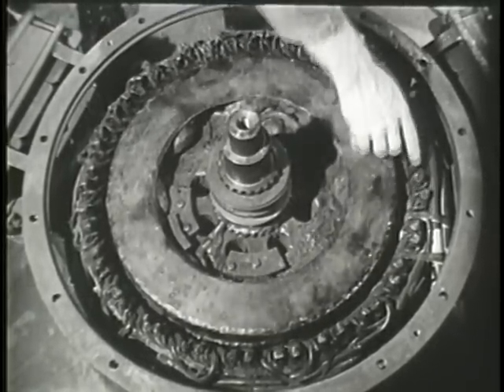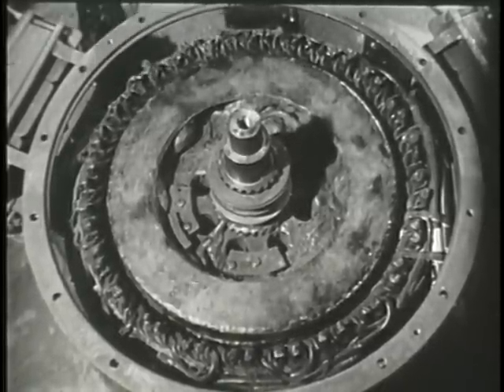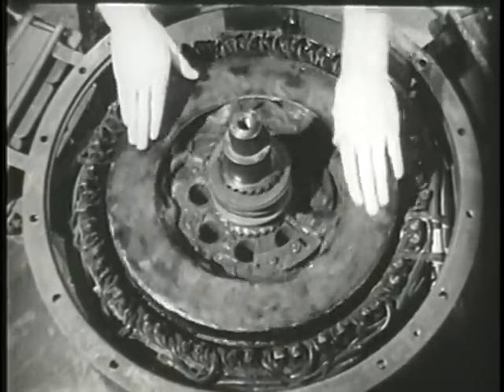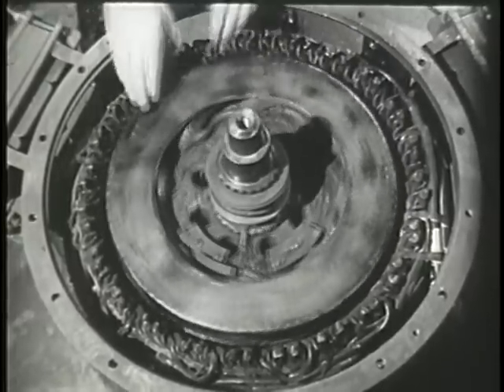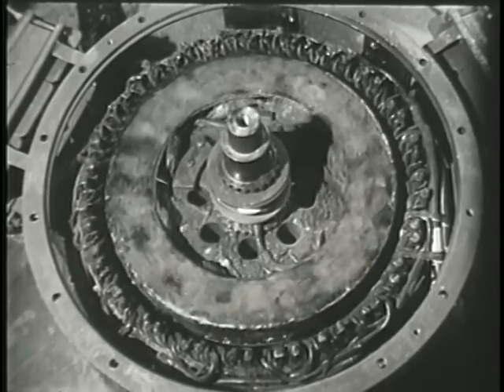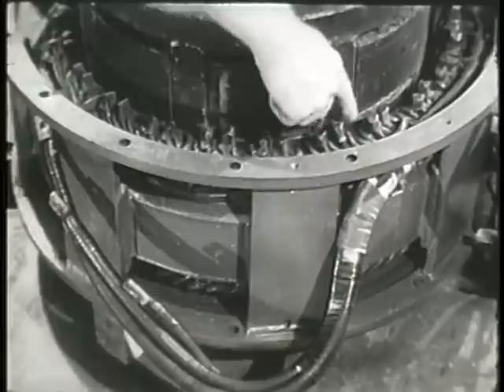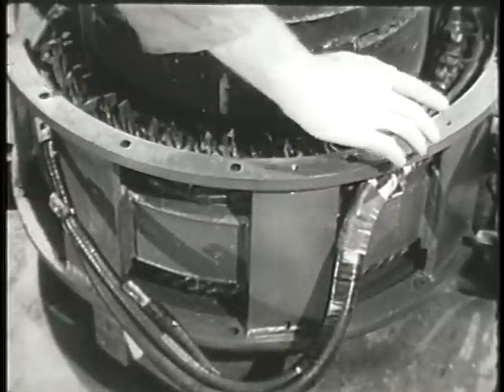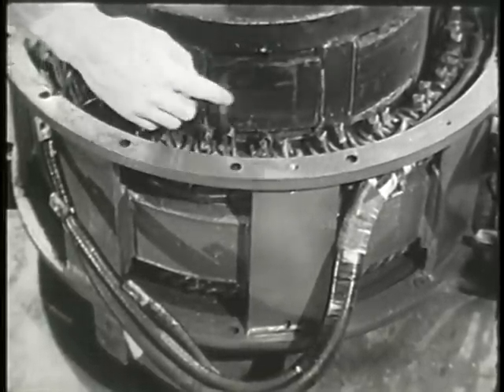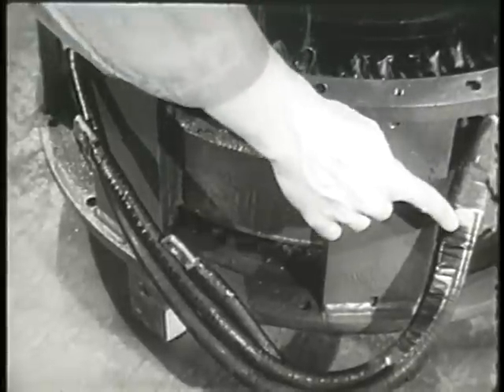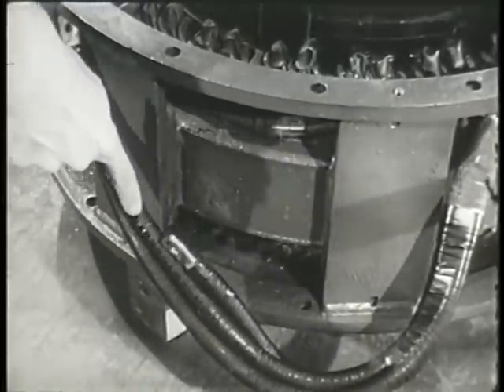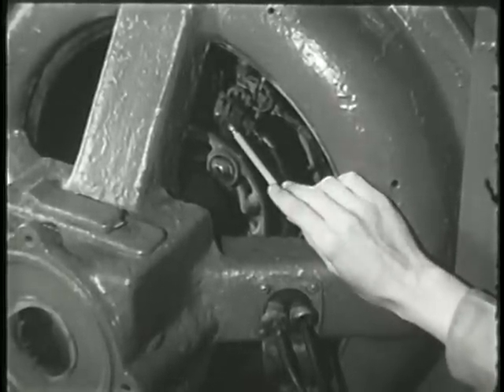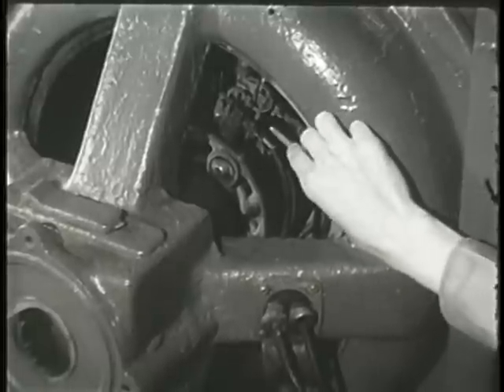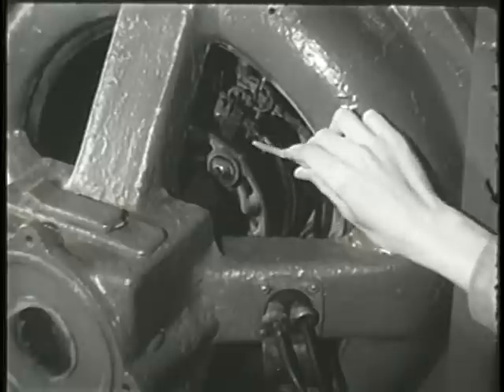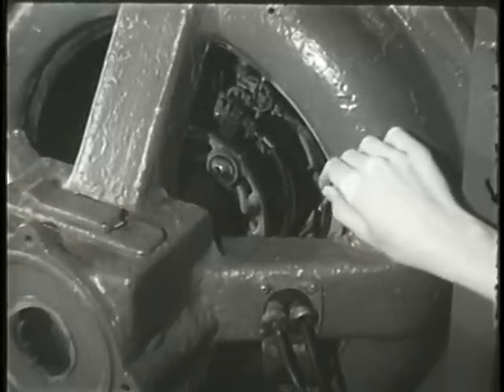Large AC generators are sometimes constructed with a stationary armature and a rotating field. Here, the coils of the armature are set around the circumference of the yoke. The poles of the field rotate within the armature to avoid the use of slip rings and to obtain direct connections to the load. Brushes and slip rings are used, however, to connect the AC generator to the outside low voltage DC source needed to excite the field. Sparking brushes at low voltage does not represent a serious problem.